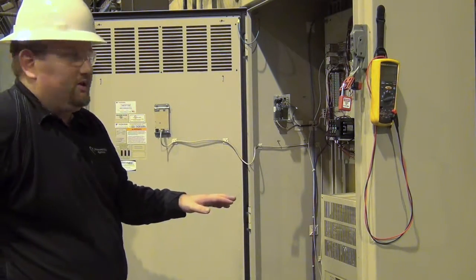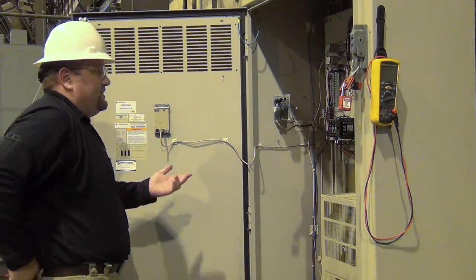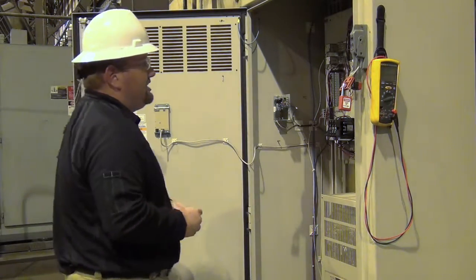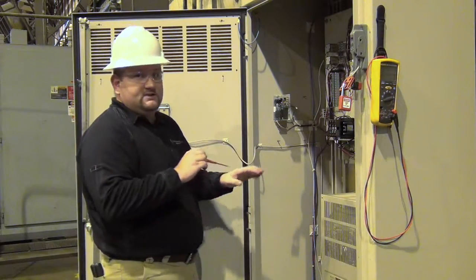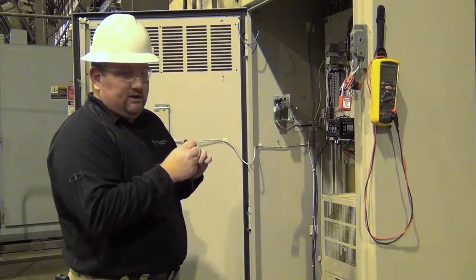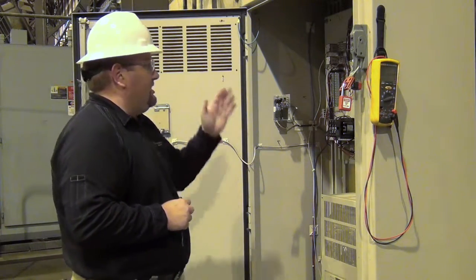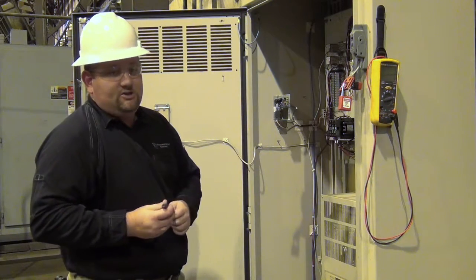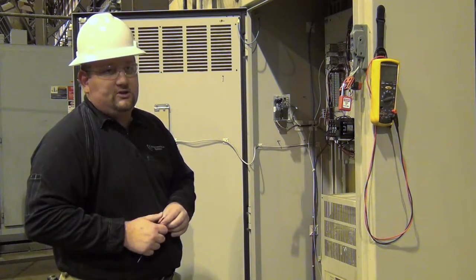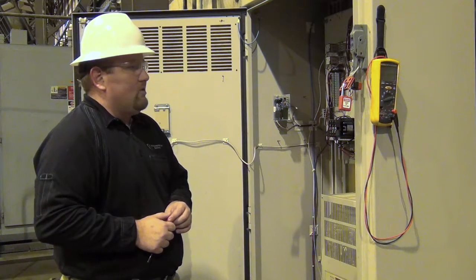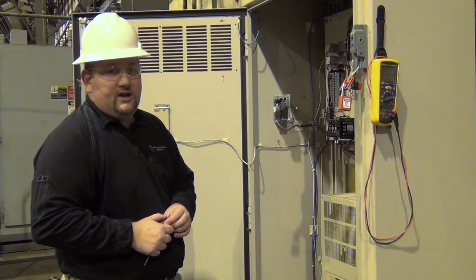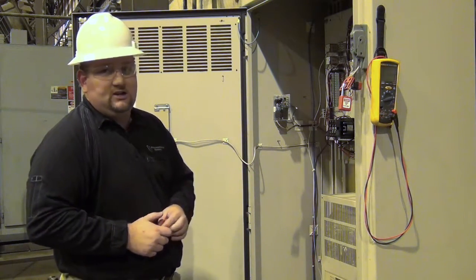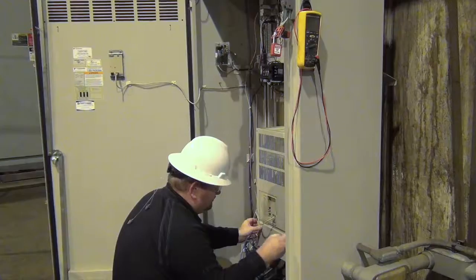Again, verify that all your circuits are dead before doing this. And just take a screwdriver and give it a little bit of a snug. Make sure there's nothing loose. Give a little pull test on the wire. Make sure that there's nothing loose. Between power connections and control terminal connections, having a wire come loose and create an arc event is actually one of the biggest killers of drives that we see in our business.